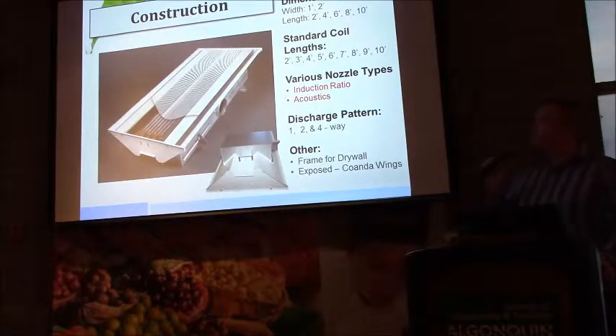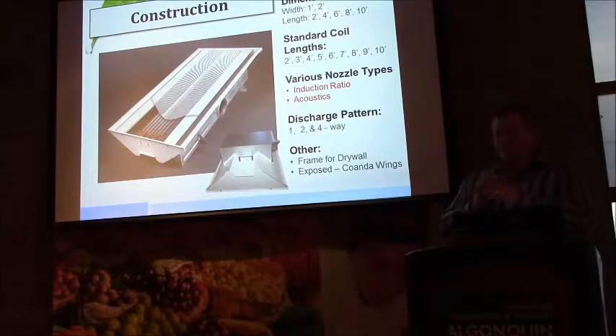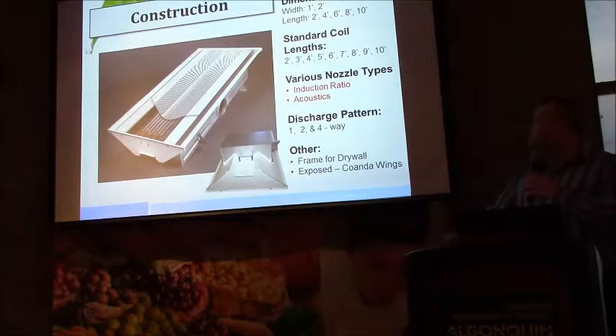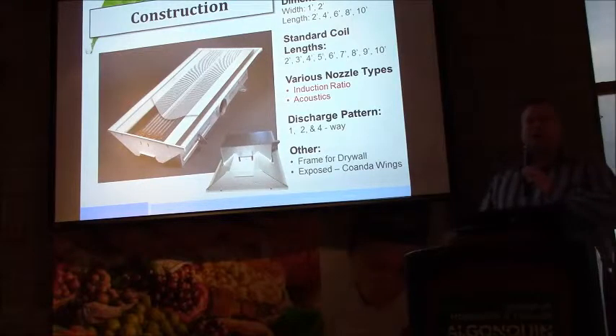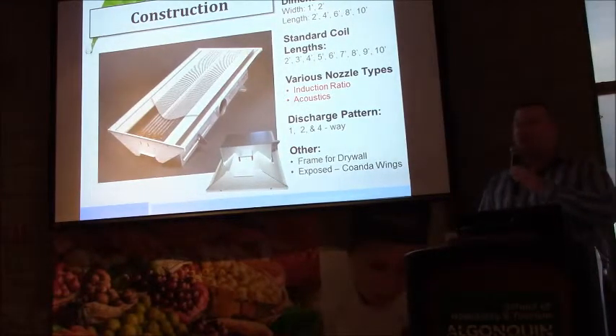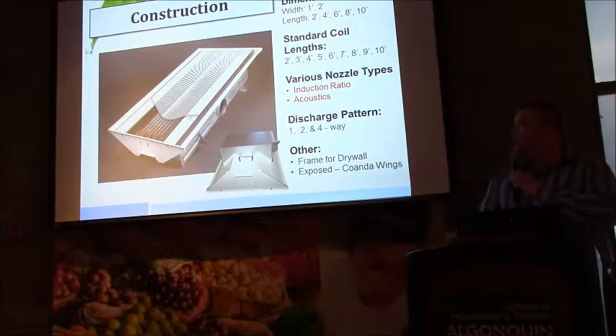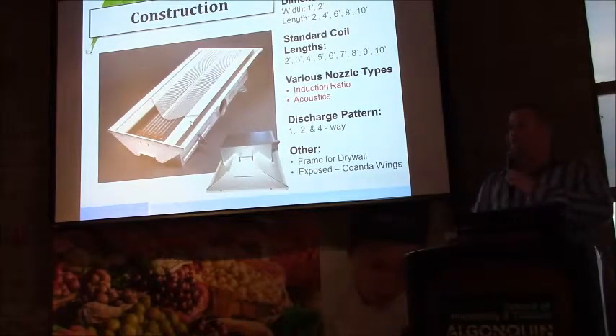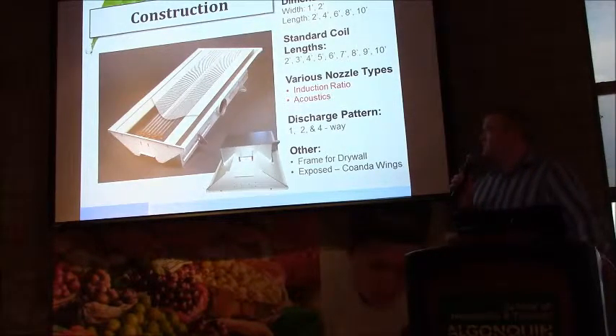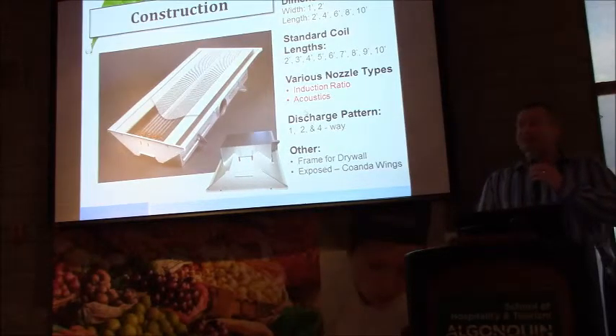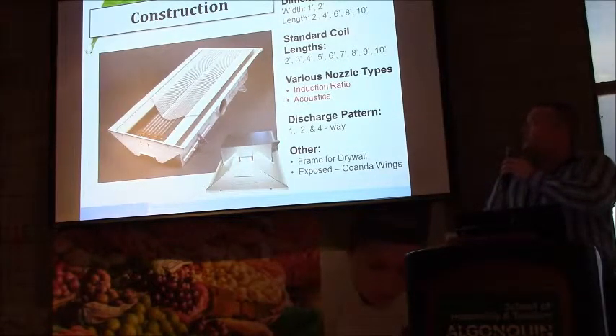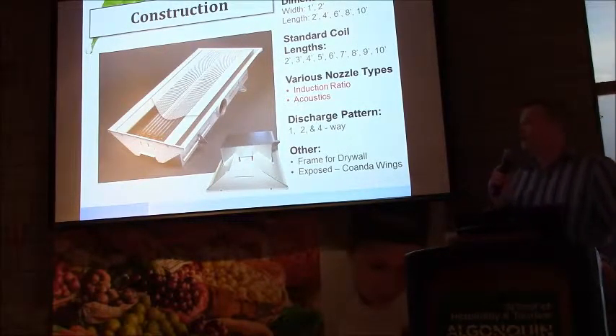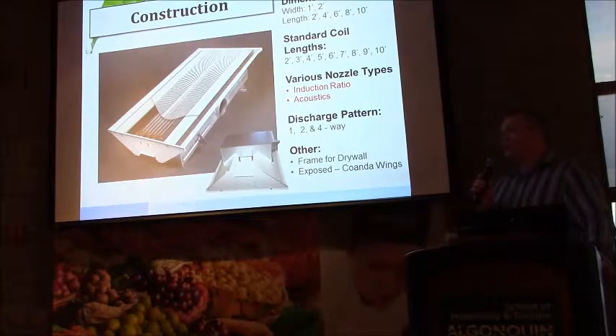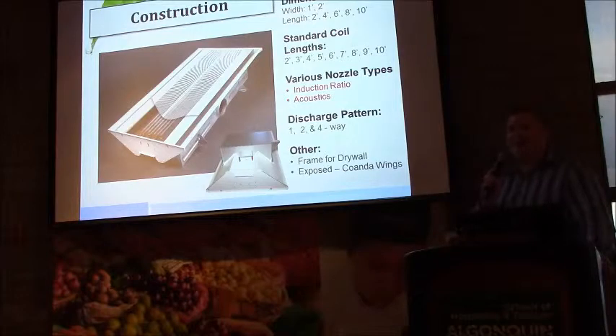This is a beam that's turned on its back so that we can see the internal components. This is a two-way discharge beam. Oftentimes beams are placed into a T-bar ceiling grid, and for the incremental cost of the installation, we yield more capacity out of a 2-foot wide beam generally than we would see with a 1-foot wide beam, although they're available for aesthetics as well. Here's a cutaway of the coil, with the doors, which generally integrate to create the linear slot diffuser. So as the air leaves the beam, it effectively operates as a linear slot diffuser. And so the discharge slot here follows all the same rules and methods of distributing air to the space as we're accustomed to when we consider it to act as a linear slot diffuser.